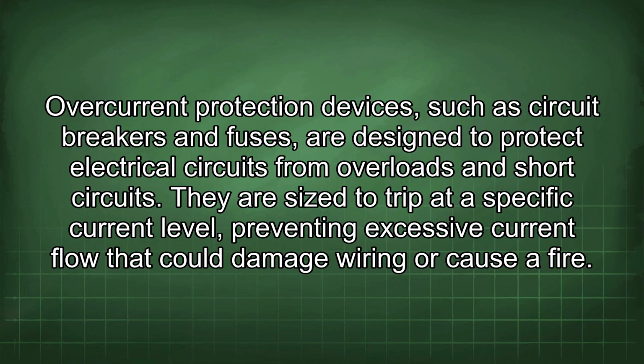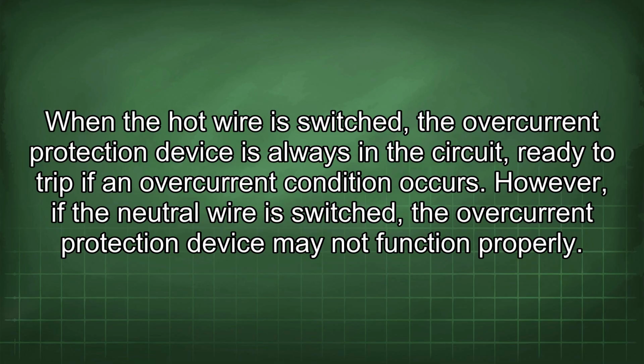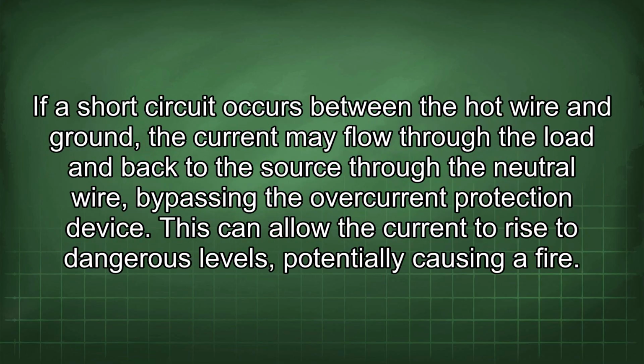Overcurrent protection devices, such as circuit breakers and fuses, are designed to protect electrical circuits from overloads and short circuits. They are sized to trip at a specific current level, preventing excessive current flow that could damage wiring or cause a fire. When the hot wire is switched, the overcurrent protection device is always in the circuit, ready to trip if an overcurrent condition occurs. However, if the neutral wire is switched, the overcurrent protection device may not function properly. If a short circuit occurs between the hot wire and ground, the current may flow through the load and back to the source through the neutral wire, bypassing the overcurrent protection device. This can allow the current to rise to dangerous levels, potentially causing a fire.